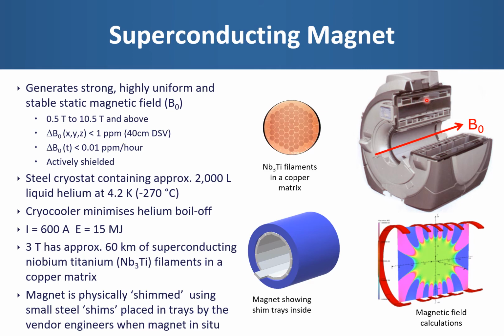The current runs in the opposite direction in these coils, and that helps to cancel the fringe field from the main magnet coils. Active shielding also means that the fringe field falls off very rapidly with distance, which means siting the magnets is much easier, but it does mean there are quite steep spatial field gradients around the magnet, which can potentially increase safety concerns.